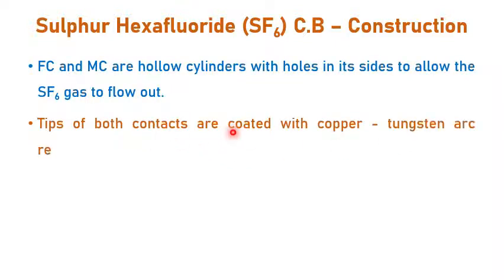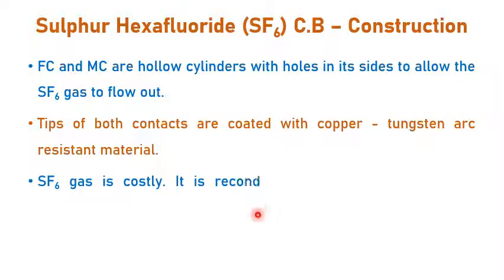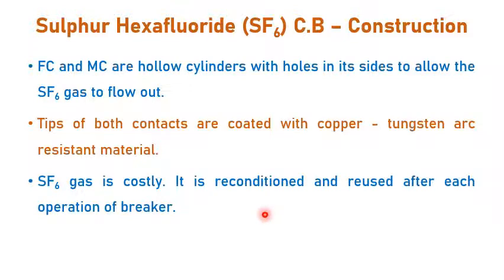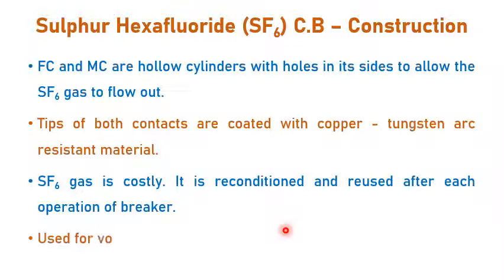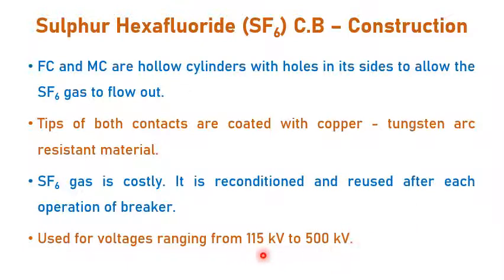The tips of both contacts are coated with copper and tungsten arc-resistance material, so the contacts remain safe even if the arc is struck often. Since SF6 gas is costlier, we can recondition and reuse it after each operation of the breaker, unlike mineral oil in an oil circuit breaker where the oil has to be replaced. This makes it suitable for high voltage operations ranging from 115 kV to 500 kV.